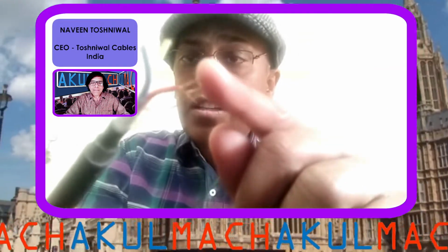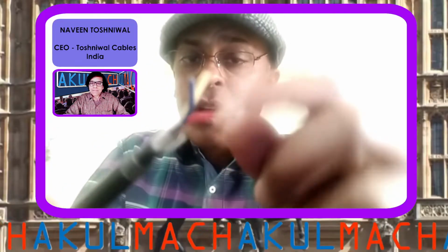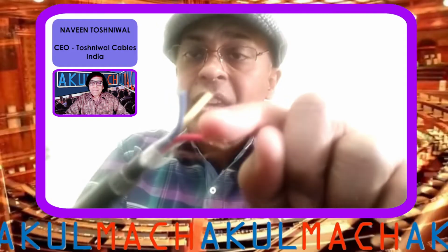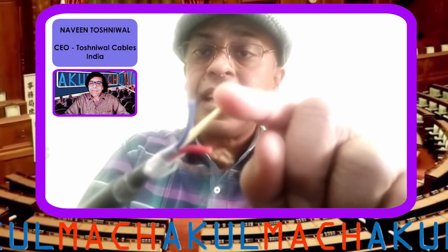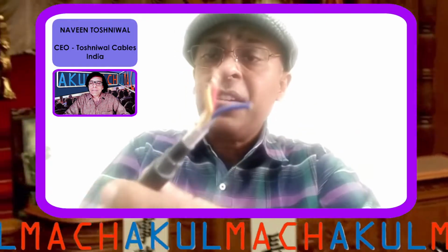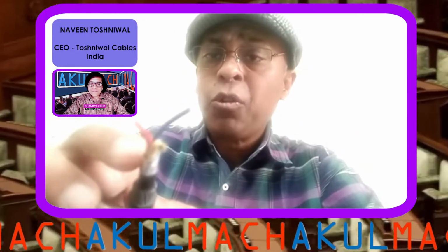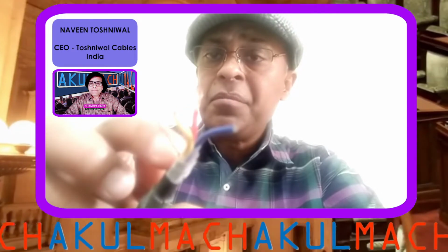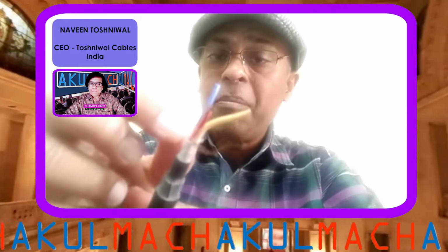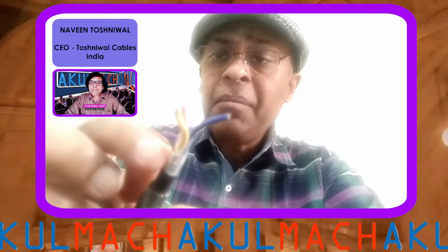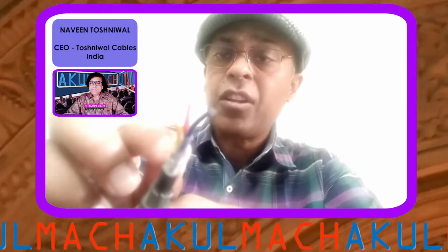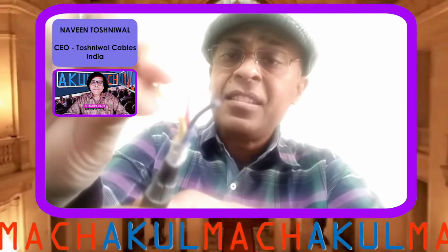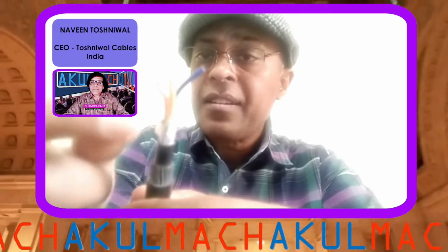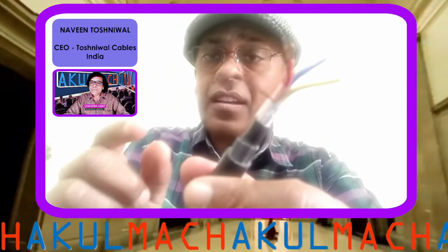Now, this has a conductor with copper strands, and then you have the insulation on this, which can be PVC or any other material as required at the site. Then we have one shielding over here, which is a taped aluminum foil. It is a combination of polyester and aluminum, a metallic tape with polyester insulation on top. And this is the earthing wire. We call it the drain wire. This drain wire is used for earthing the metallic portion of the tape to the ground.